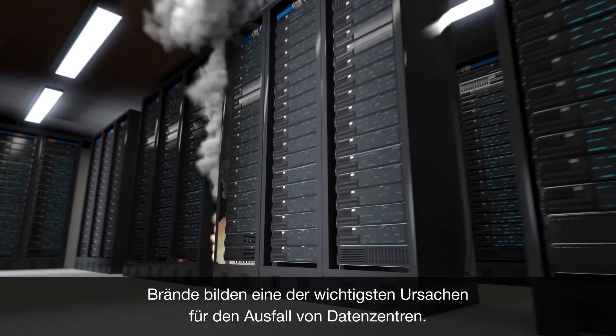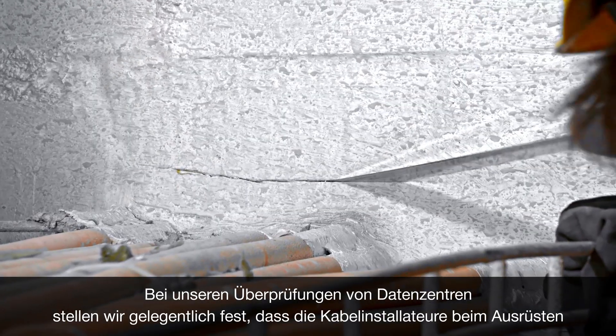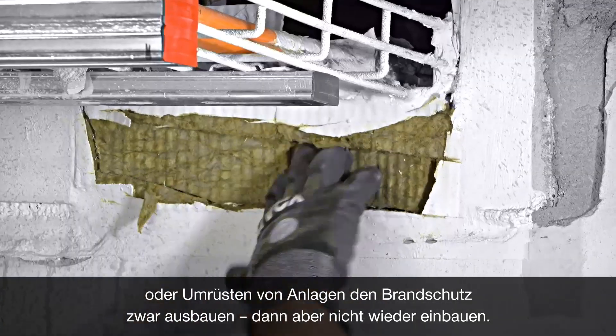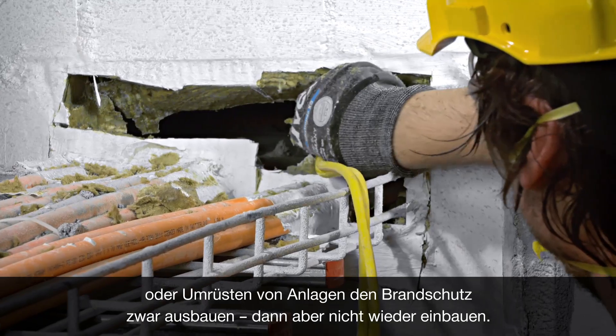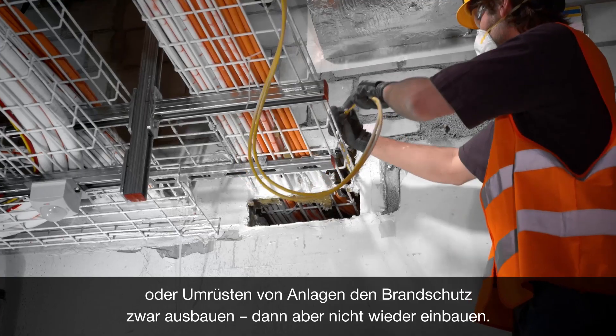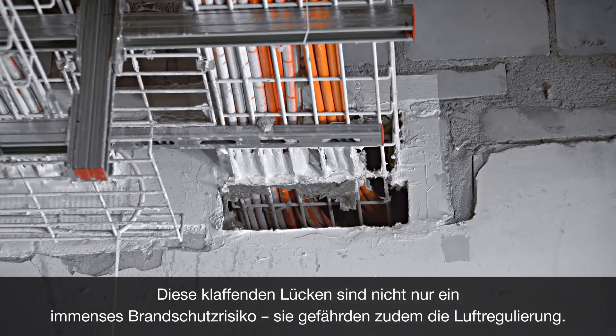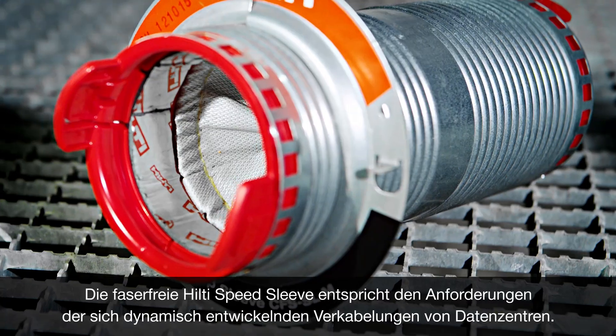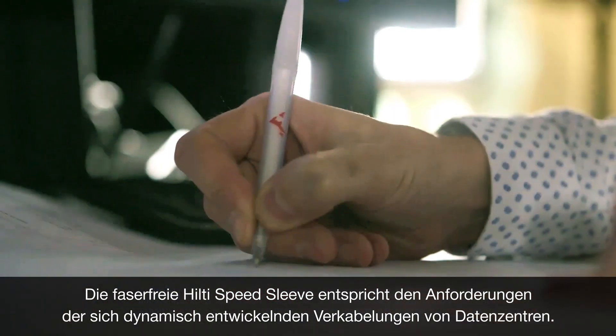Fire is one of the most significant causes for data centre failures. In our work auditing data centres, we find that cable installers who are going to refit cables or install new cables into an existing facility will take out fire stopping and not reinstate it. These gaping holes in the fire barrier pose not only a major risk in terms of fire, they also compromise air flow management. The fibre-free Hilti Speed Sleeve was designed to meet the specific needs of dynamic cabling environments like data centres.